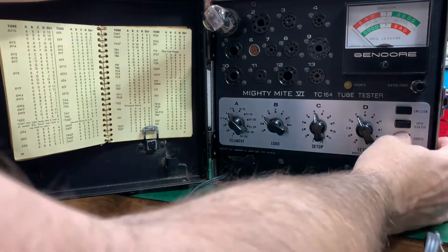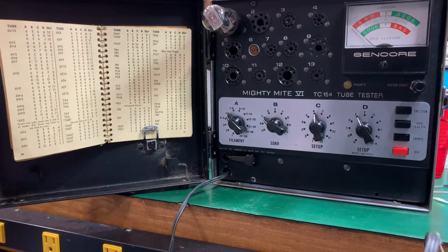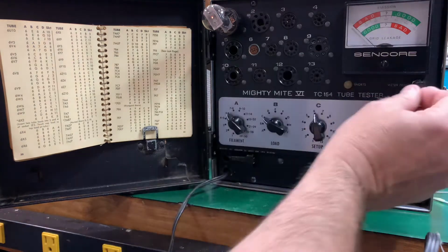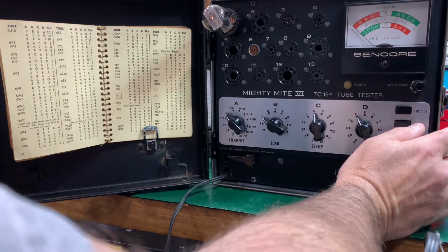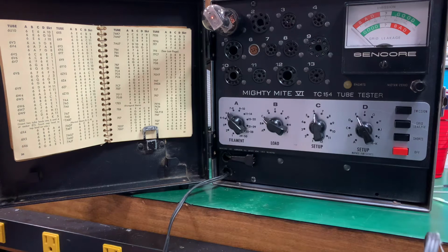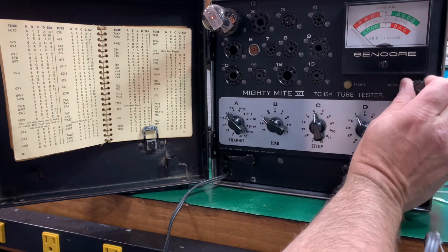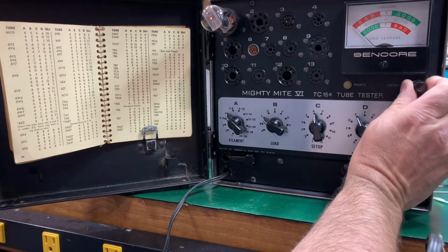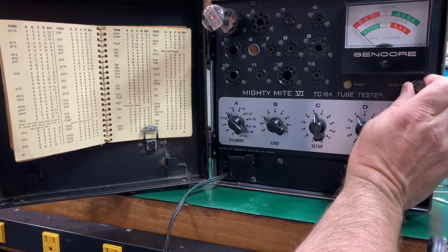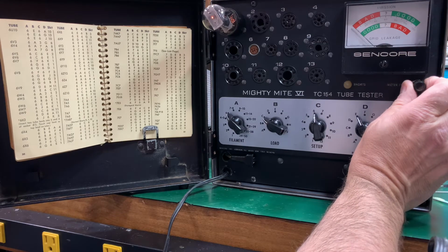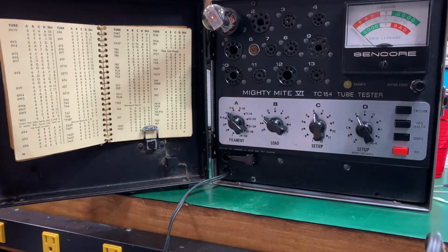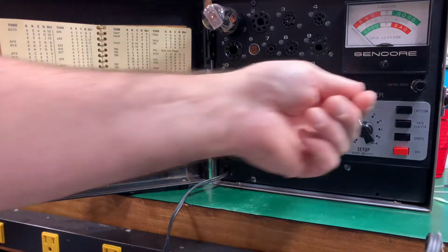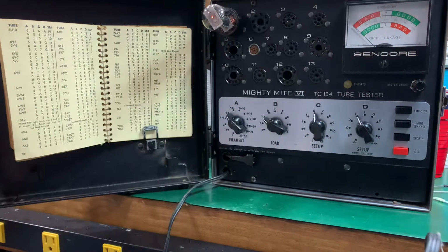Now we're going to go to short. When you go to short, this is where you adjust your line voltage for whatever voltage this is plugged into. Not all line voltages are the same - could be 110, 115, 120, 122. So when the calibration is done, it won't affect anything as long as you have set this for your line voltage. So there we are, right on 0. If someone buys this, they got 115 volts, they turn that up, bring it to 0. It's right in calibrated spec.